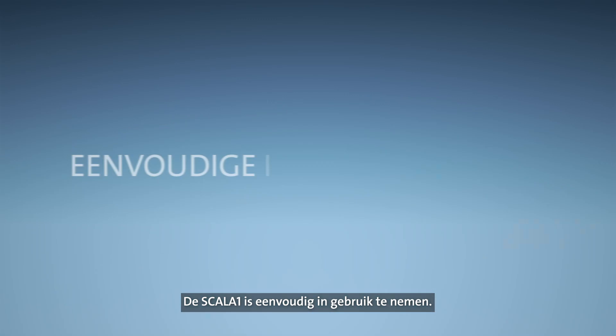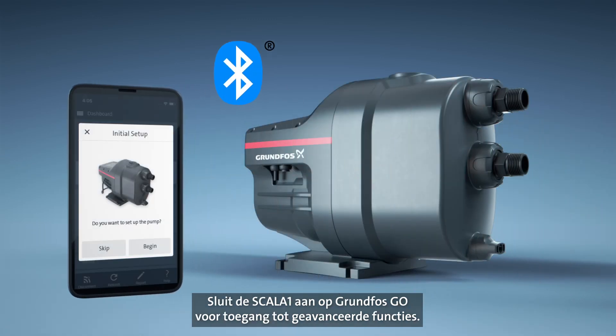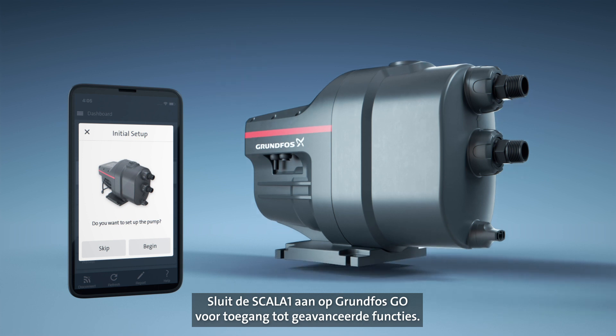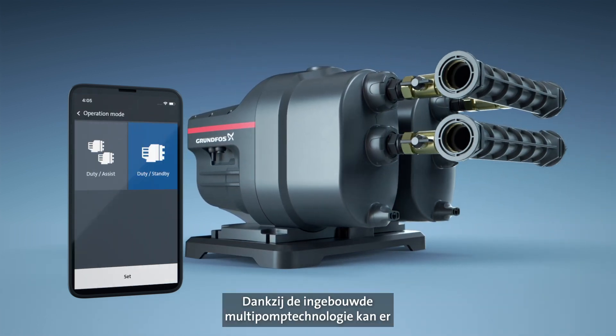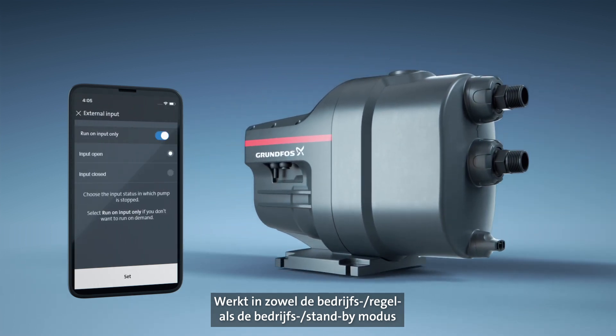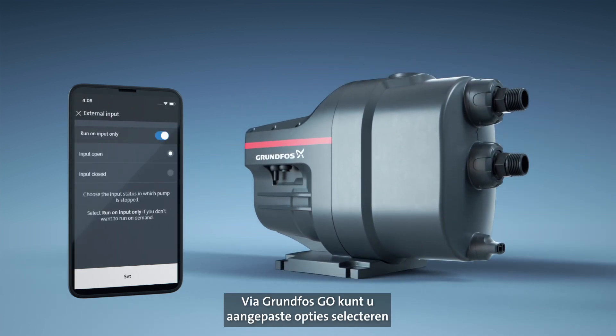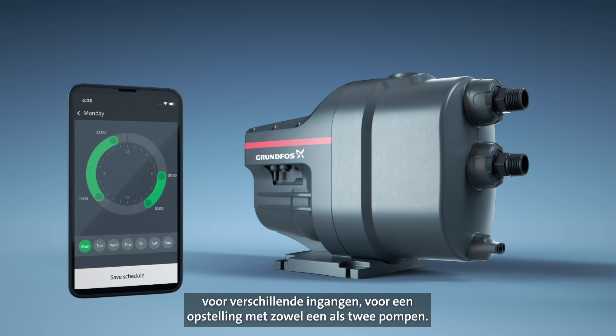SCALA1 offers easy commissioning. For advanced features, simply connect SCALA1 to the Grundfos Go app via Bluetooth to start the setup. Built-in multi-pump technology enables quick connection between two SCALA1 pumps in either duty assist or duty standby mode, increasing the boosting capacity. Via Grundfos Go, you can also select customized options for different inputs for both the single and the twin pump setup.